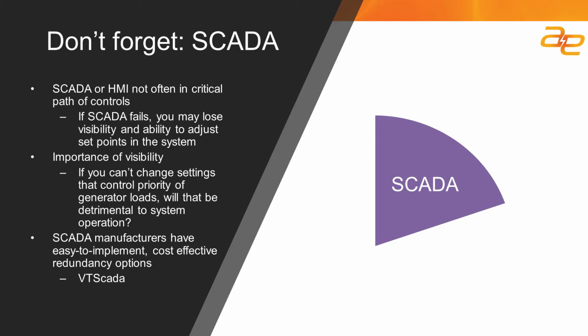The control system itself, the networks, and the instruments certainly make up the majority of the control system, but the SCADA system is probably the tool used to visualize what's happening within the control system, to manage set points at a high or supervisory level, to respond to alarms, and to determine whether a change in how the control system operates is needed.